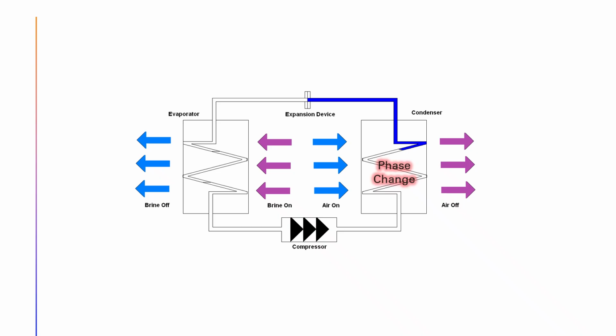So the hot gas enters into the condenser, and because we know that within the condenser we have a phase change where it turns from a high pressure gas, hopefully, down to a high pressure medium temperature subcooled liquid leaving, and then it hits the expansion device, where there's a sudden pressure drop. As it leaves the expansion device, it's a massive pressure drop, so it tries to turn back from a liquid to a gas and becomes a two-phase mix.